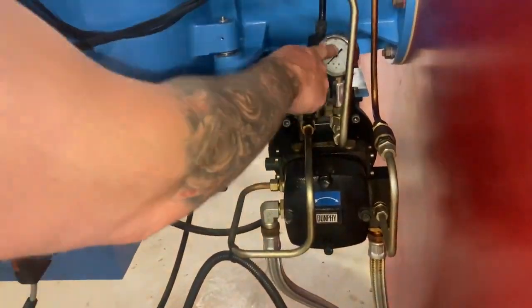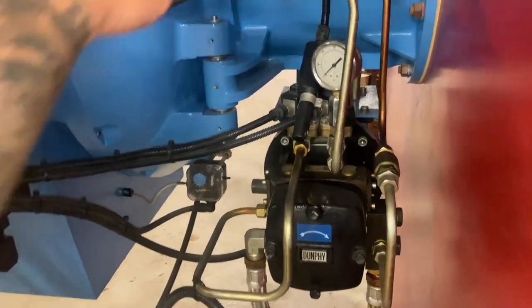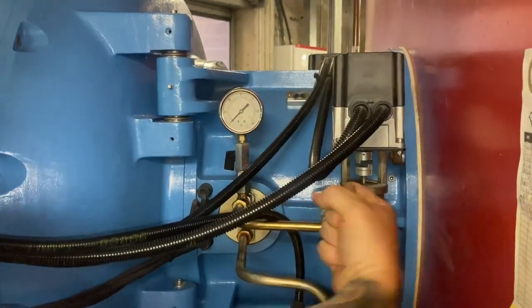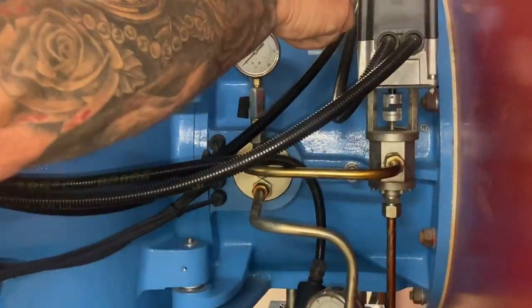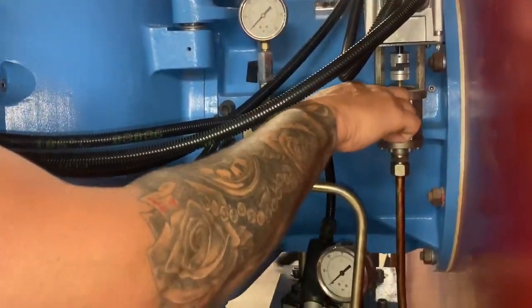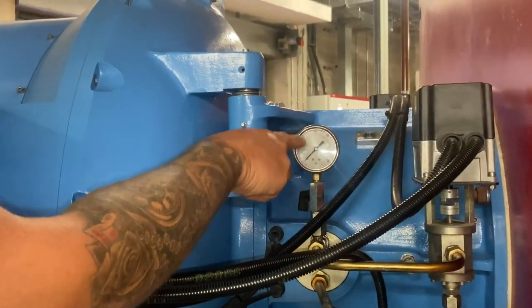So oil pressure comes in there, fixed speed on that. So that will just rotate, and all this does to adjust the oil, the same again, it's a proportional valve. That there will get a signal on the CAN bus to say, right, I need to open up proportionally to whatever demand we've got, and that will relate to a pressure showing on that gauge.